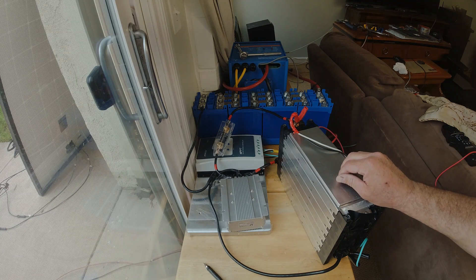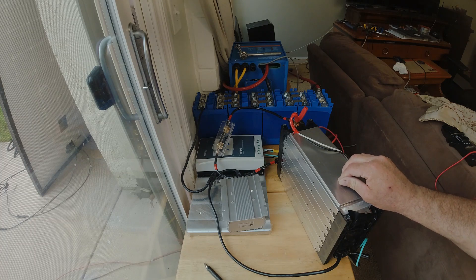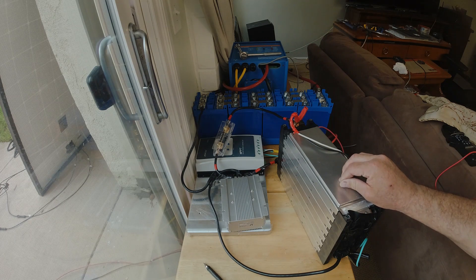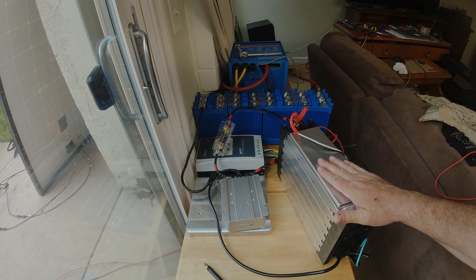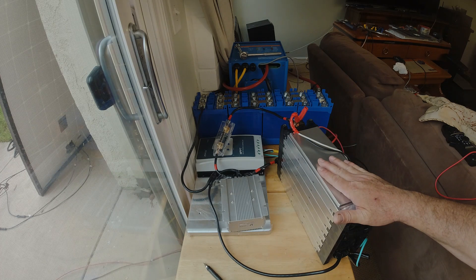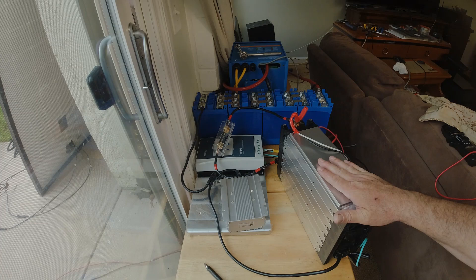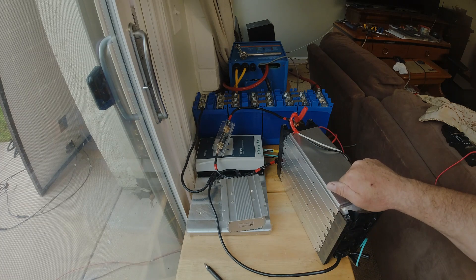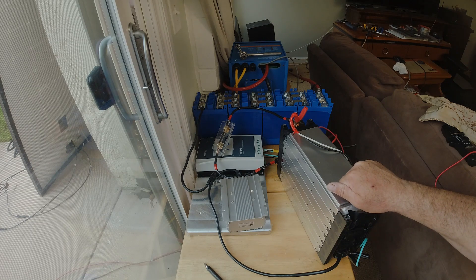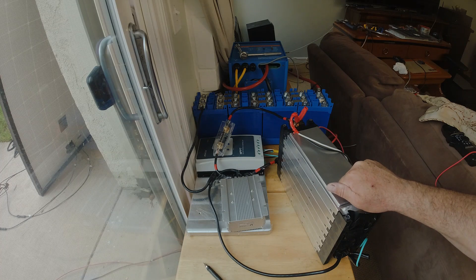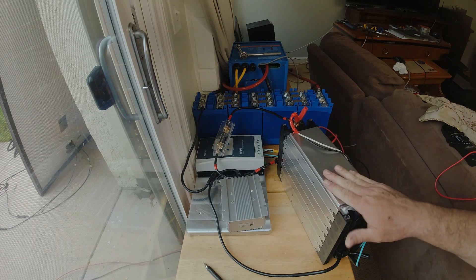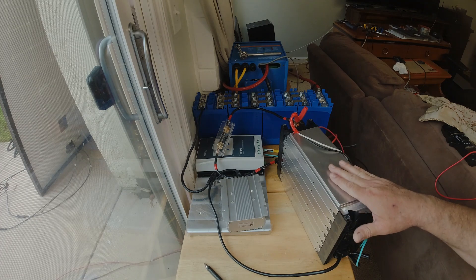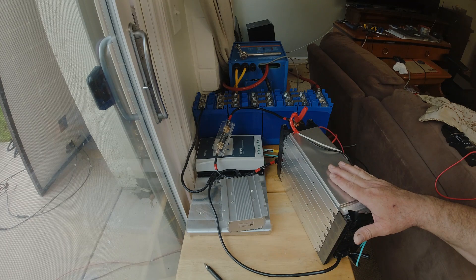So these under the gel profile, the bulk charge would be at 28.4 volts and the float charge is at 27.6. That's about perfect for these. Now if you really want these guys to last a long time, you're not going to charge them all the way, you're going to charge them like 85% or 90%. But frankly this is a test bench scenario.